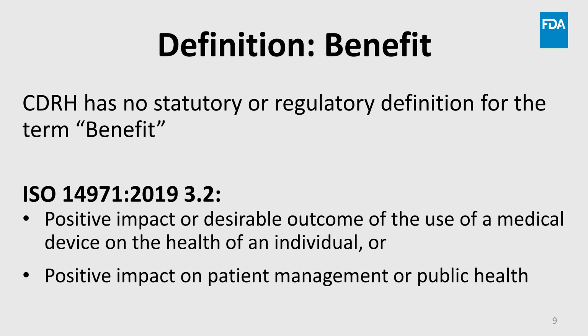However, right now we'll define something new that was added to the ISO 14971-2019 standard. And that is the definition of benefit. Benefit is the positive impact or desirable outcome of the use of a medical device on the health of an individual, or a positive impact on patient management or public health. As with risk, CDRH has no formal definition for the term benefit.